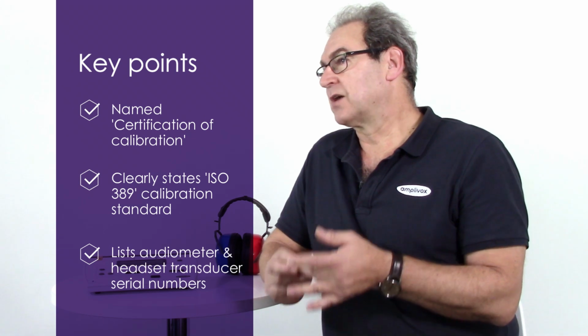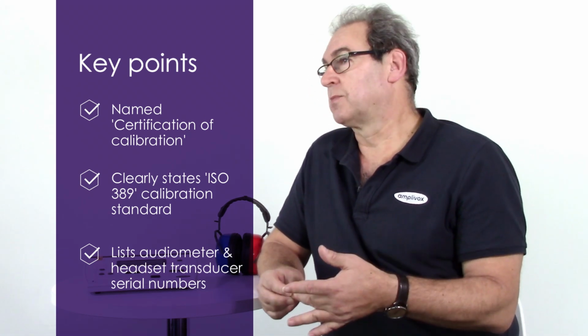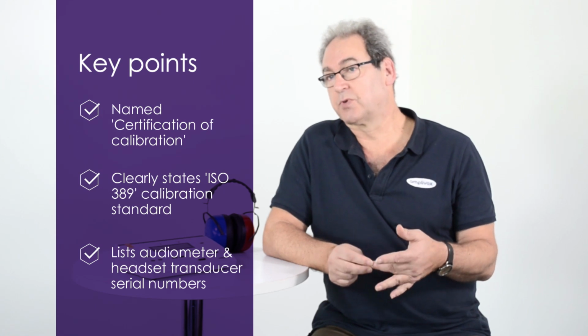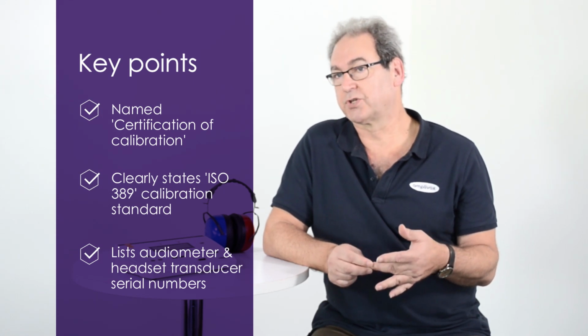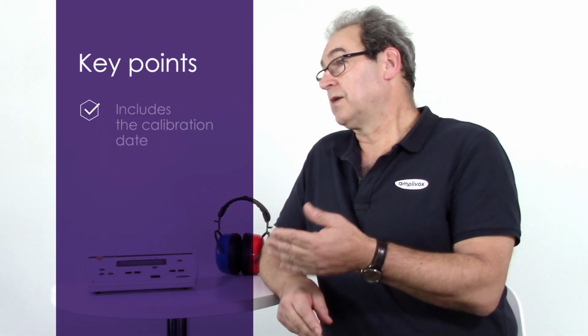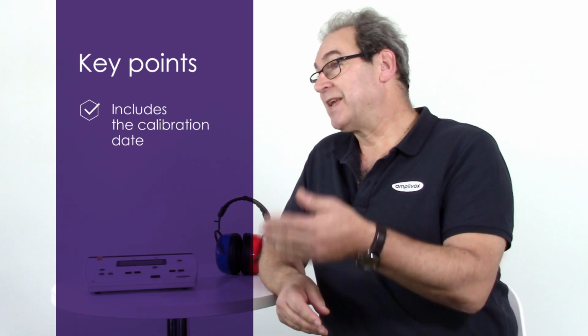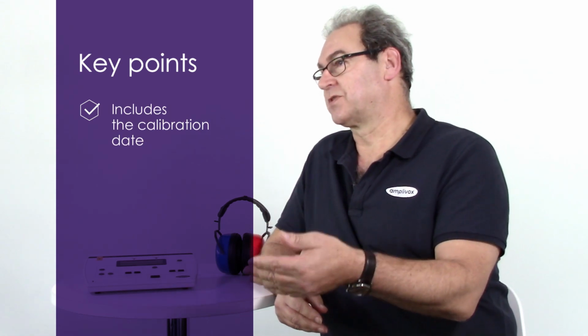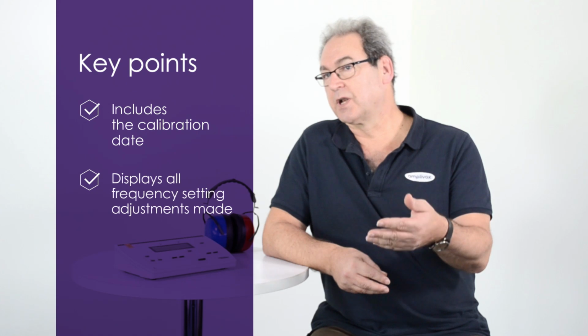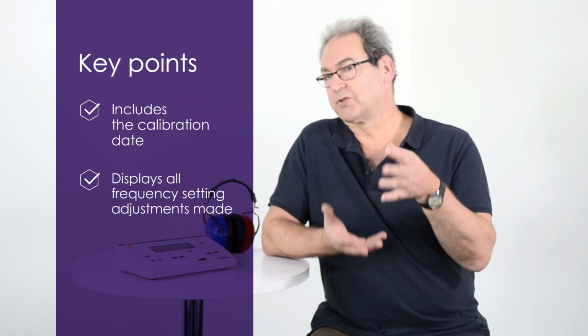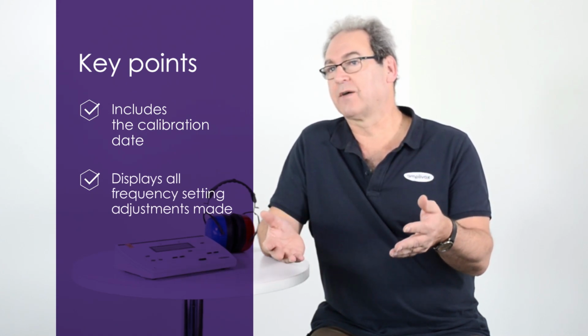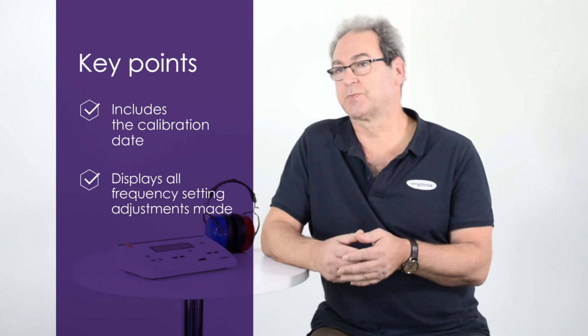Thirdly, the actual serial number of the audiometer is listed, as are the two serial numbers for the earphone transducers. Then, it sounds obvious, but we actually need a date of calibration on the certificate. And finally, with a calibration certificate, we normally have before and after adjustments, so everyone can actually see the value of calibrations and that they actually meet those particular standards.